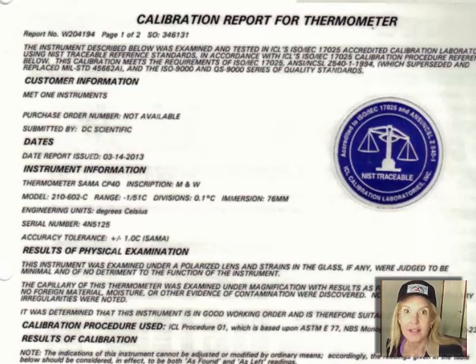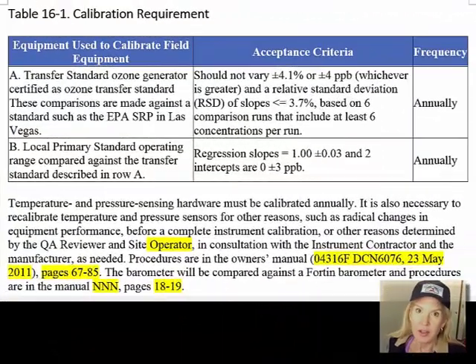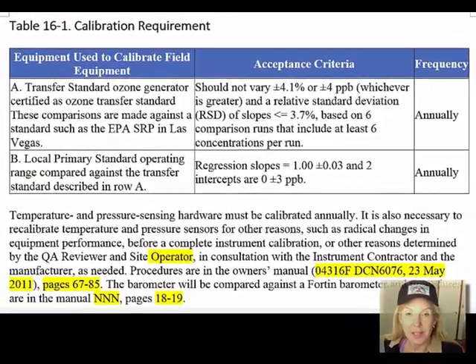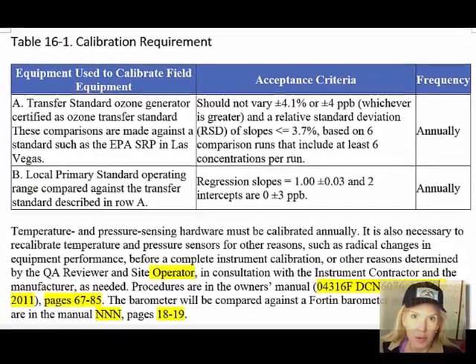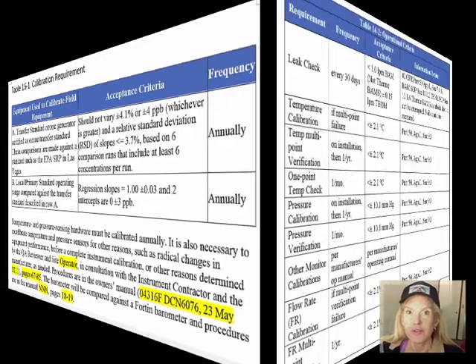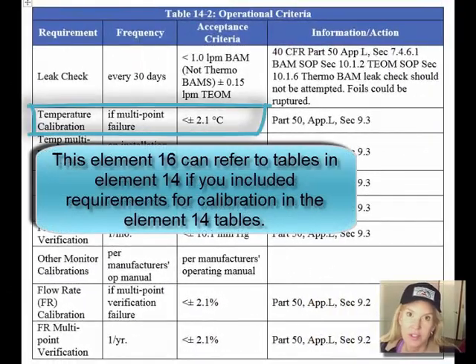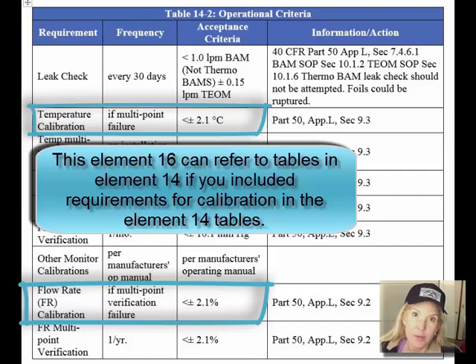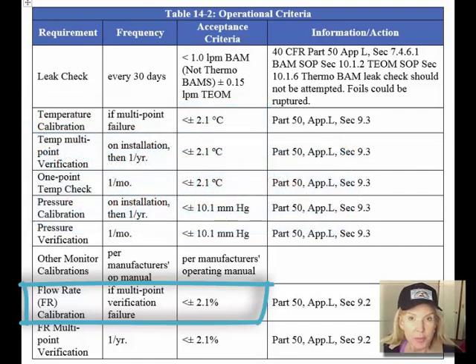Now, in some cases, you can do that depending upon what parameters and what instruments you're using. In general, calibration is required annually. Sometimes calibration is not required unless an instrument fails verification. In other words, it's not operating within limits, or for some other reason, like you have to move it or it's been shipped, then calibration is often called for.